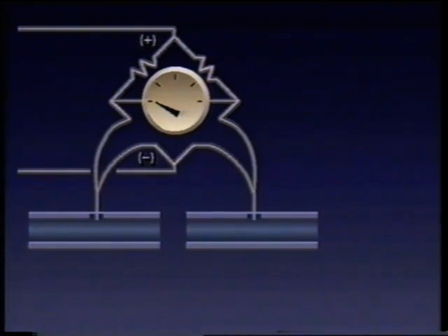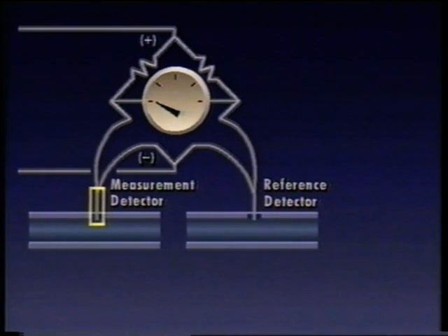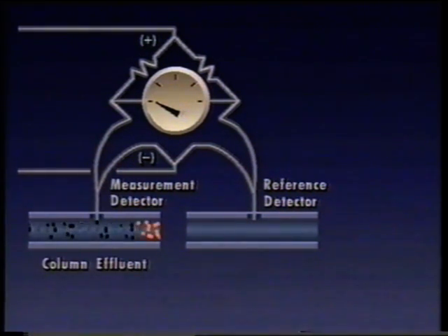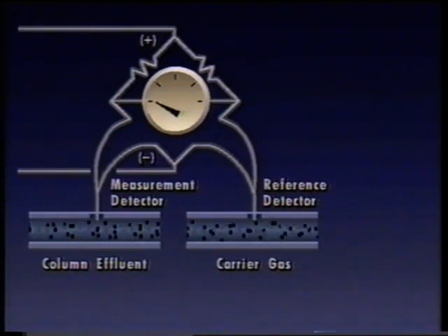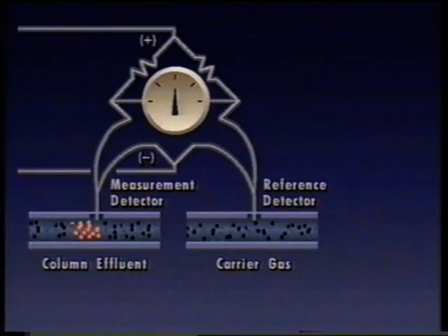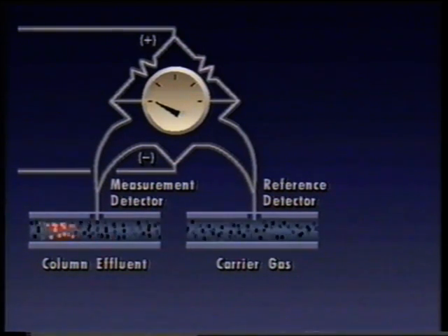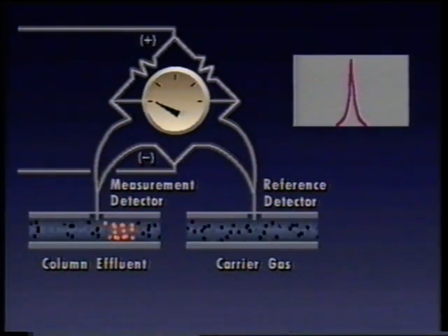A thermal conductivity detector uses two thermistors as two legs of a Wheatstone bridge. One thermistor is the reference detector. The other is the sense or measurement detector. The column effluent, which consists of the carrier gas and sample from the column, flows over the measuring detector. Pure carrier gas flows over the reference detector. Because of differences in thermal conductivity, the components and the carrier gas conduct heat and cool the thermistors at different rates. This results in changes in resistance, unbalancing the bridge, and generating a signal that represents the concentration of the sample component.